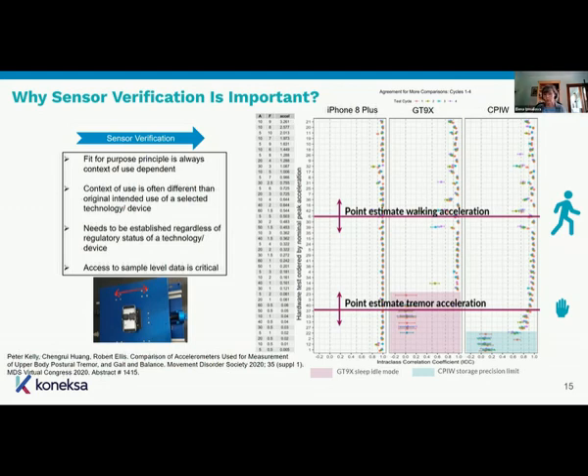devices across different accelerations. So you can see from this picture that for point estimates of accelerations observed close to what we normally expect during walk, the agreement according to the ICC is good or excellent, because most of the values are above 0.8. So all three devices, the accelerometers in all three devices, are fit for purpose to record gait and balance. But I have another data set on a lower part of this table.